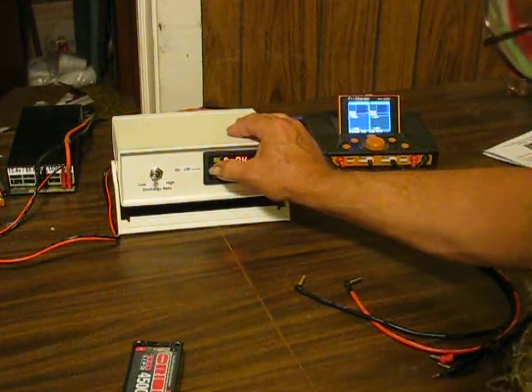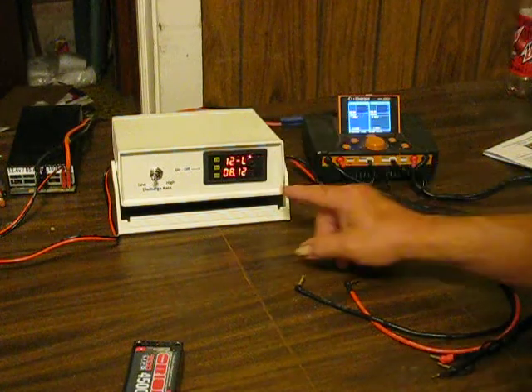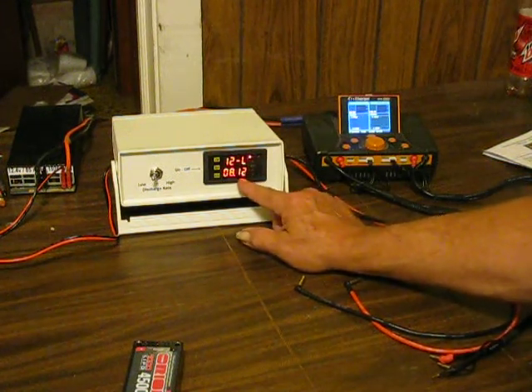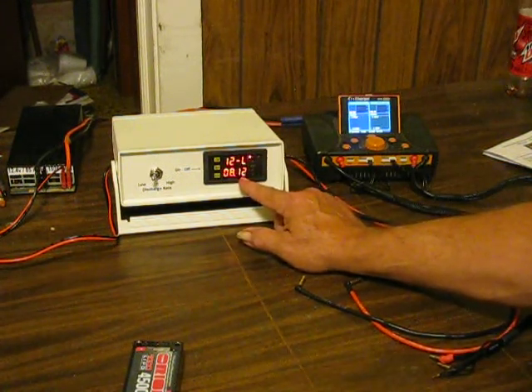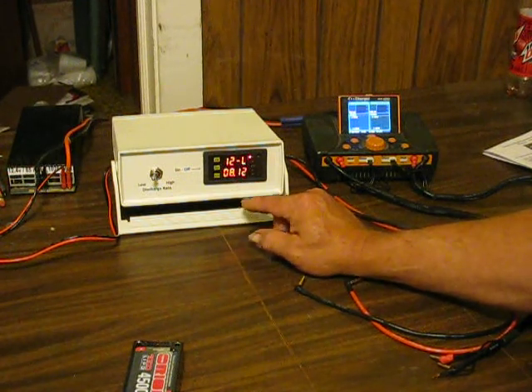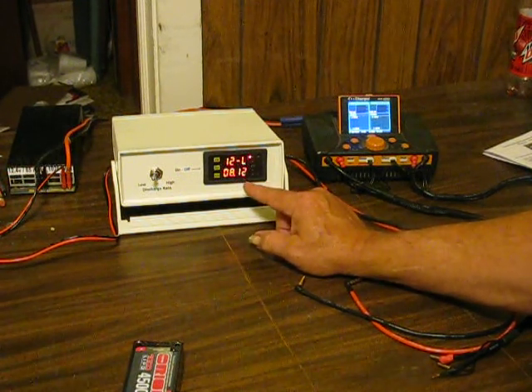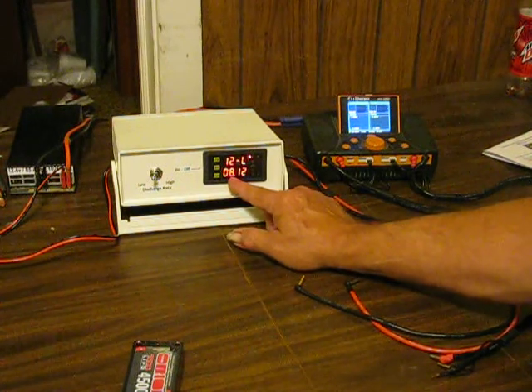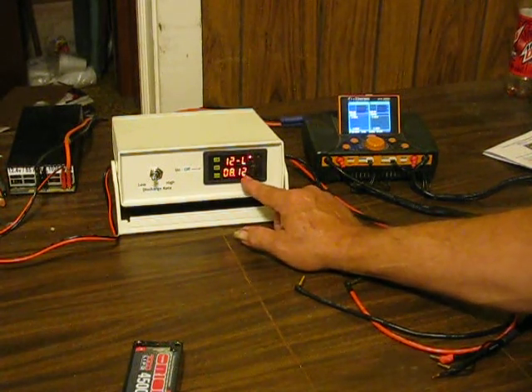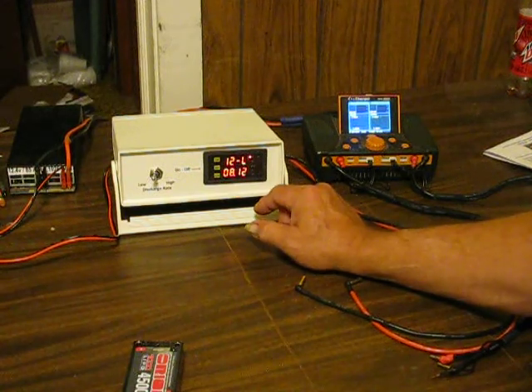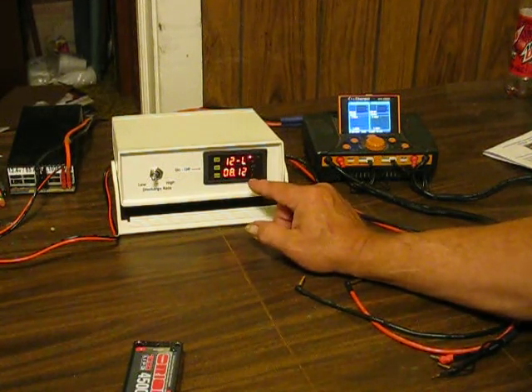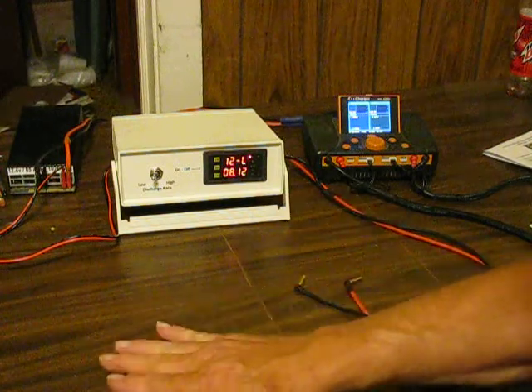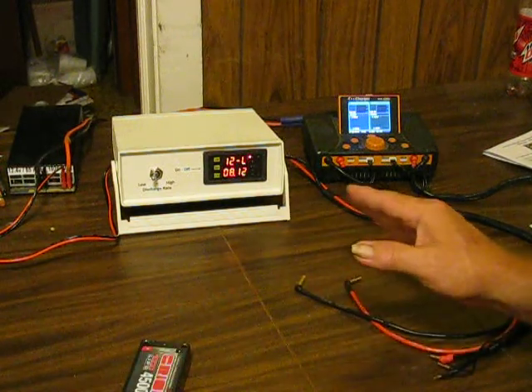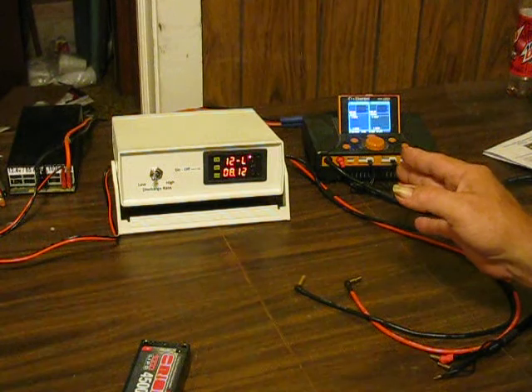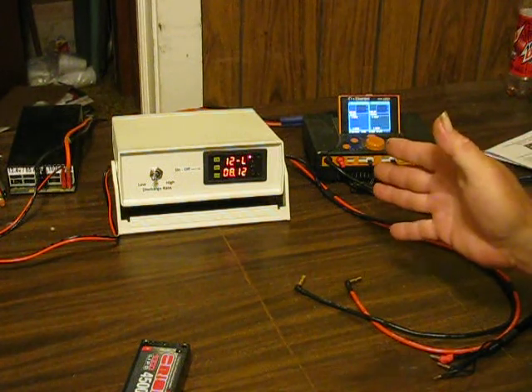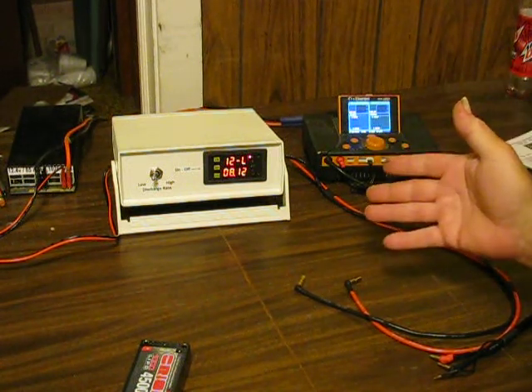Click the center button. This is your low voltage. This is the voltage you want your unit to shut off at. I personally take this number down to 6.97. That's pretty close to when the unit is not hooked up, that is, the battery is at rest, not discharging, will be anywhere from 7.2 volts up to about 7.35 volts.